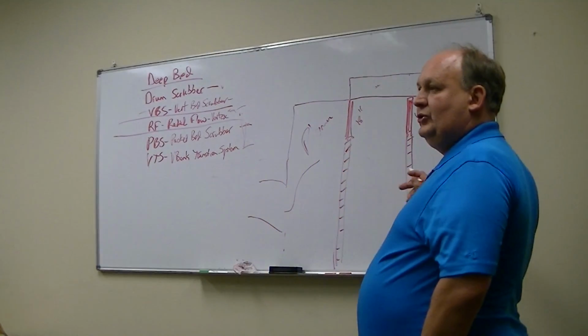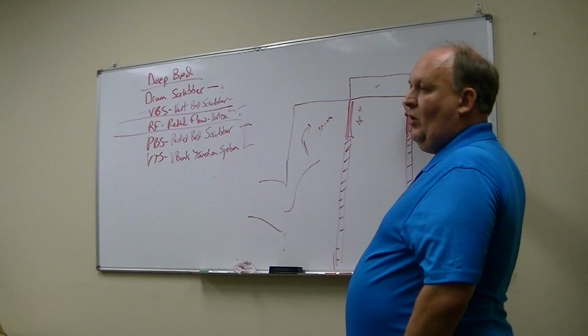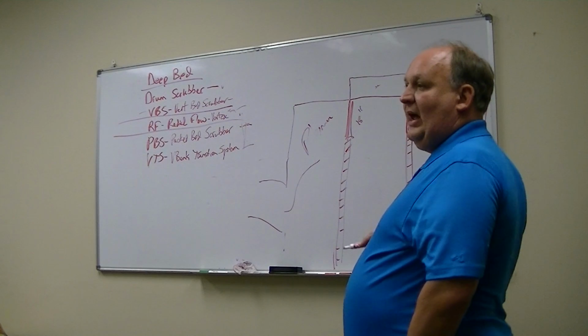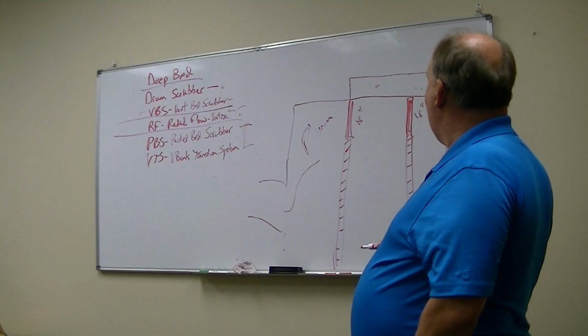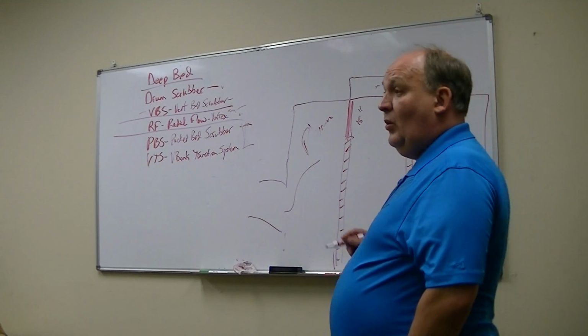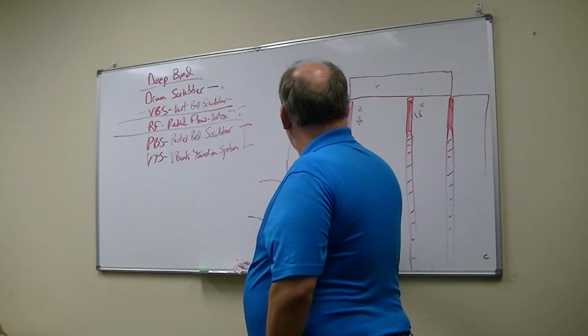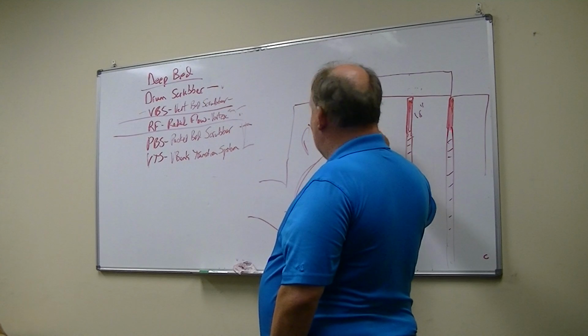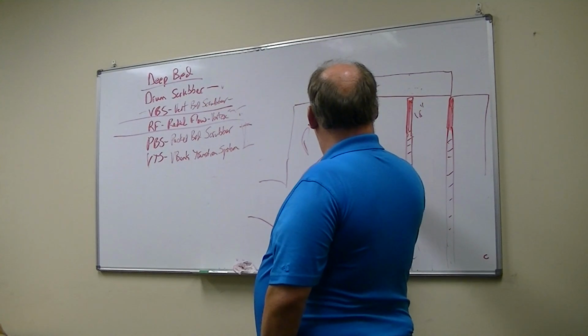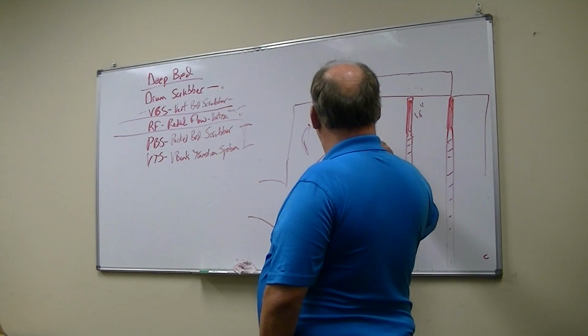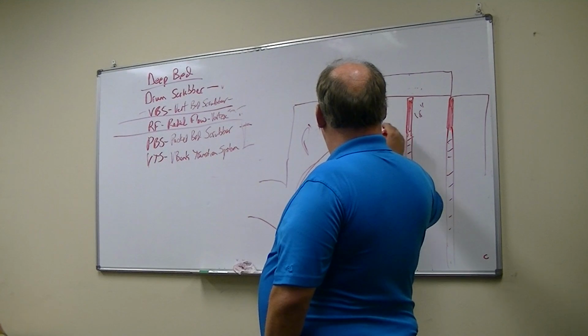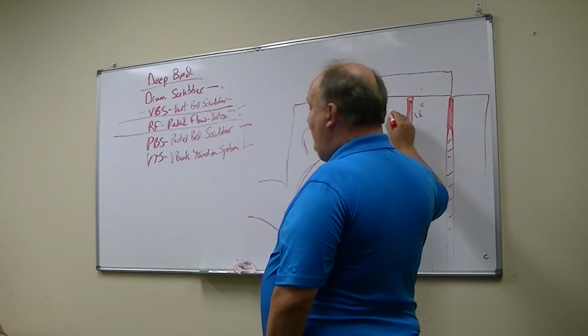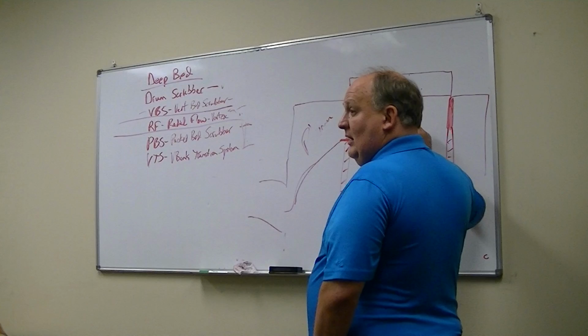They don't fill the fill chute at all. They tell the customer, you don't have to worry about filling the fill chute because we've got a baffle down here. Okay? So first of all, what happens in this system? First, the air never gets here, right? The first place the air enters is this area. So you get very poor usage of any of this media here.